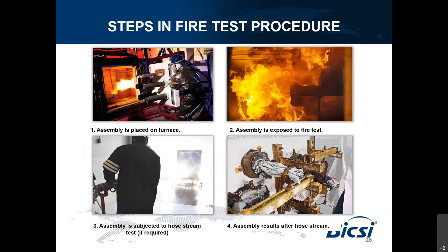For American standards, the third box is about hose stream testing, which only applies to UL related standards. They use a hose with high pressure water to test under thermal shock, checking whether the firestop material will still stay in the wall.